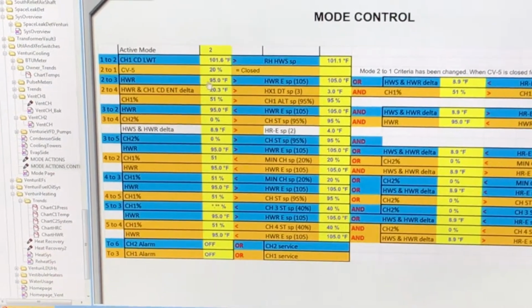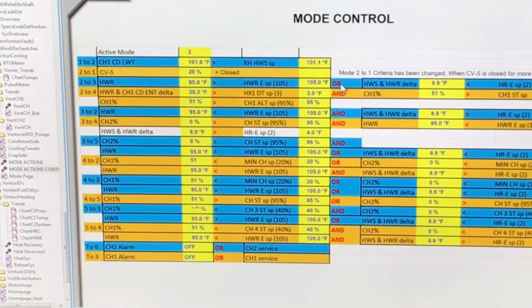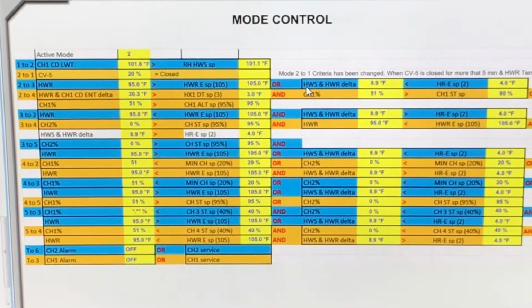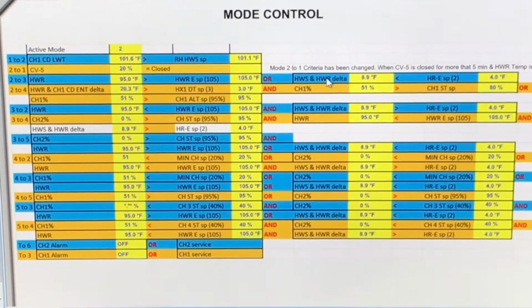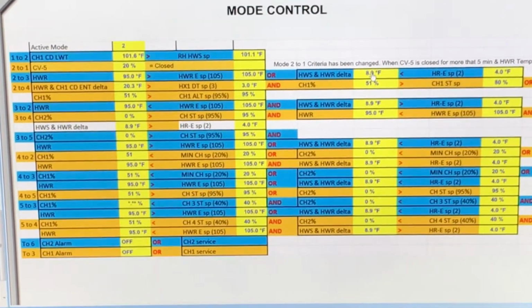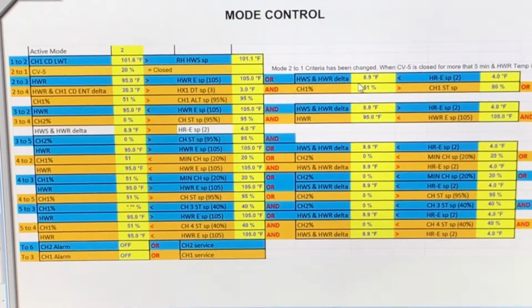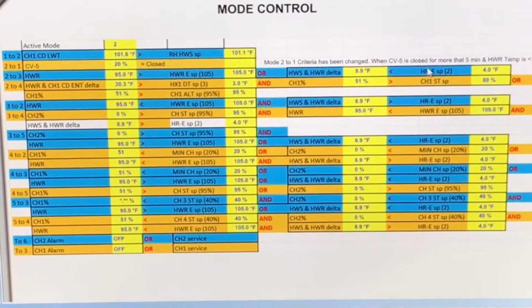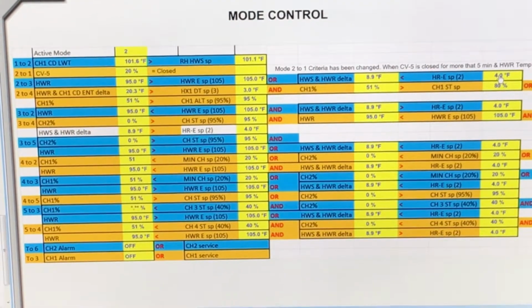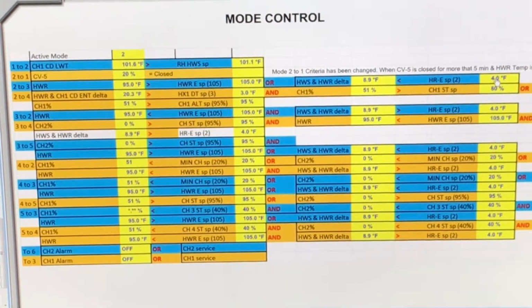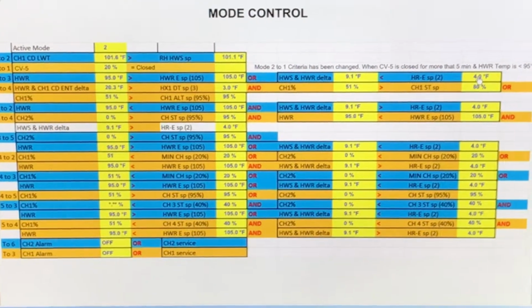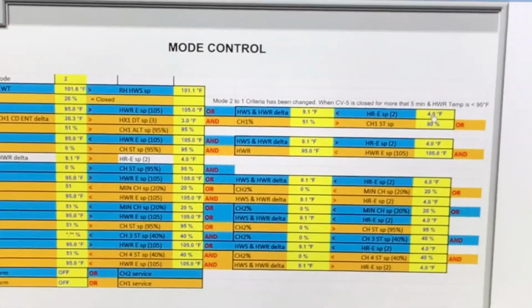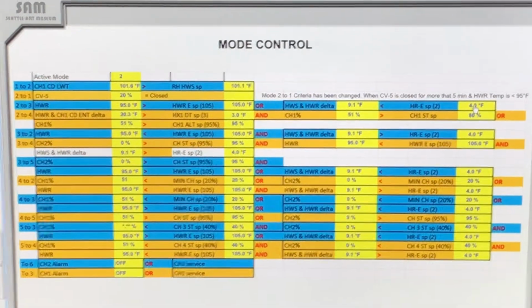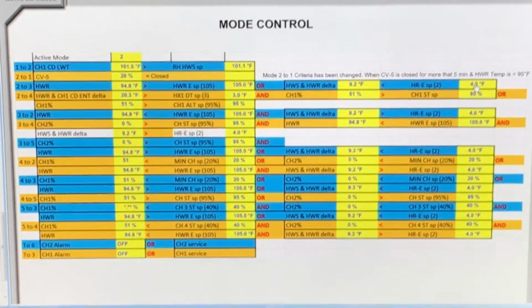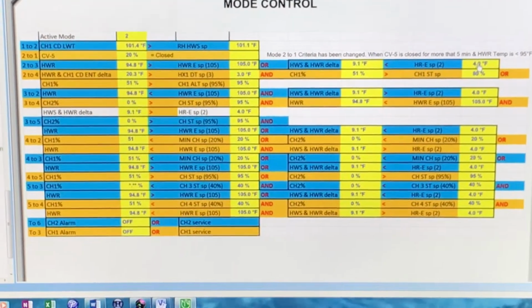This one also, from 2 to 3, could happen where the delta between hot water supply and hot water return, which is a 9-degree delta right now, is less than this set point, which is 4. If the delta is 3, then it's going to move to 3. Do you guys understand that? This was the most confusing part of the whole thing for me, the mode page. And this is where you fine tune your system.